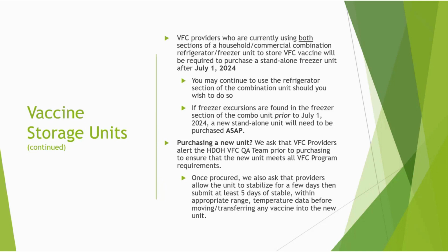Once procured, we also ask that the providers allow the unit to stabilize first for a few days and then submit at least 5 days of stable, within the appropriate range, temperature data before moving or transferring any vaccine into the new unit. This is to prevent any kind of vaccine loss that may arise from any kind of temperature excursion that occurs in the unit during the stabilization period. Next slide.